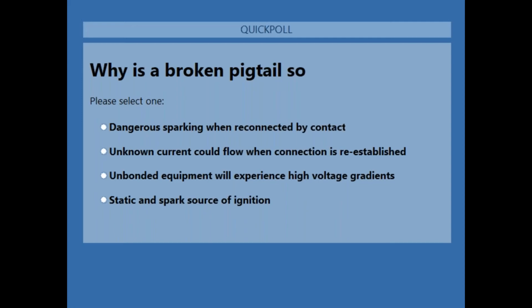Well, it could spark when it's reconnected. That could actually be a return current that's waiting to reestablish. An unknown current could flow when it's reconnected. Unbonded equipment will experience a voltage gradient, and it could be a static or spark source.